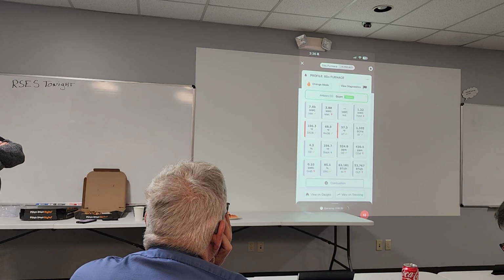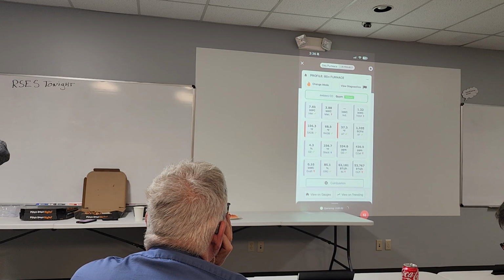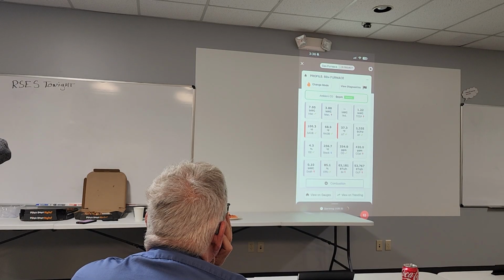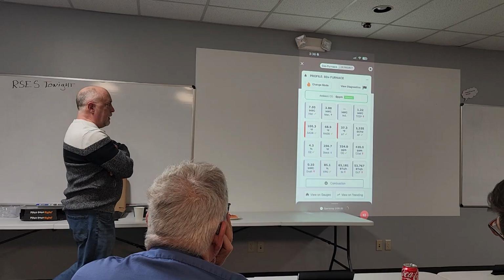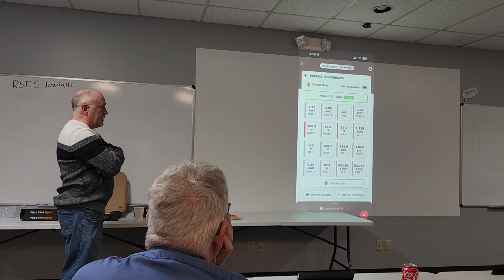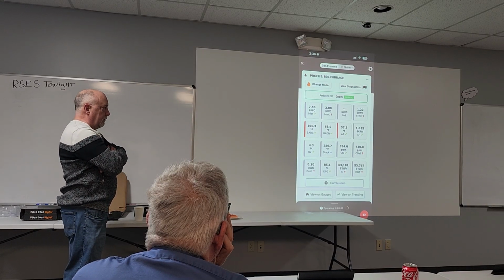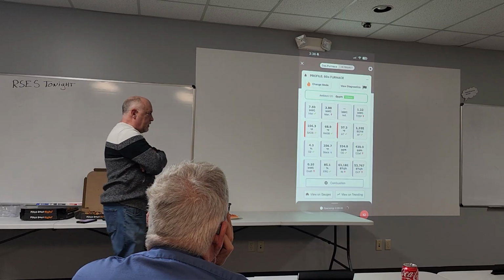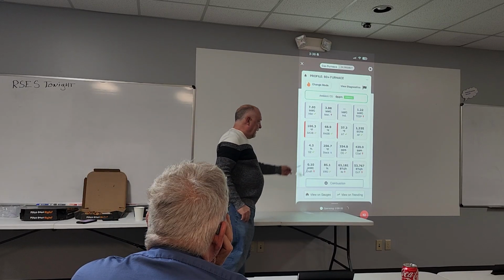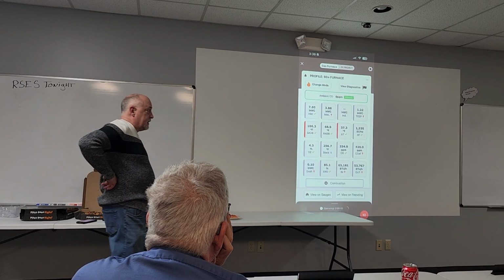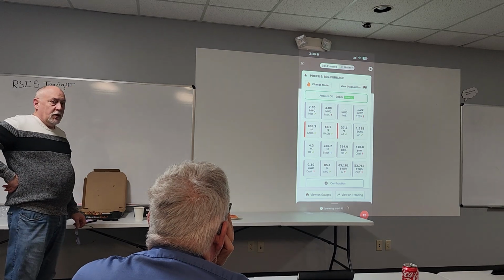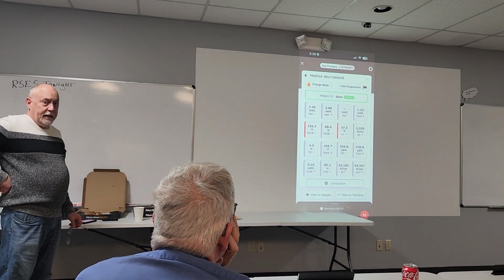Well, it's CO for sure. CO, but what else? The gas. Yeah, the gas pressure, very good. Gas pressures, yeah. So what do you think that's probably rated at? A nominal 3.5 and we're at 3.88 inches of water column. 3.9. It's a 60,000 BTU rated appliance and it's 63,000 input. So it's definitely overfired, right?